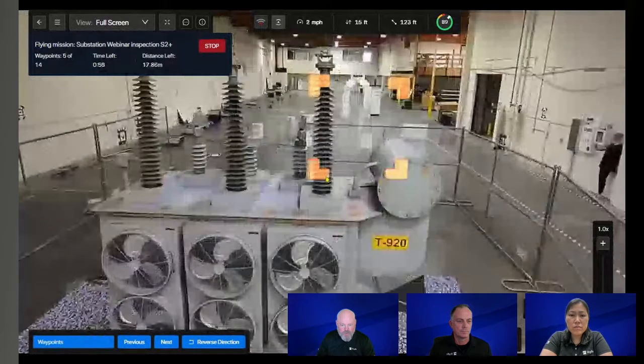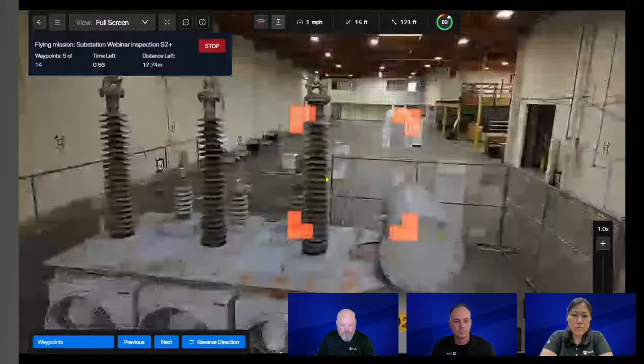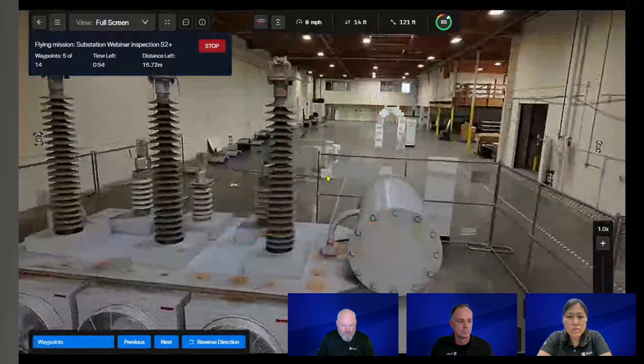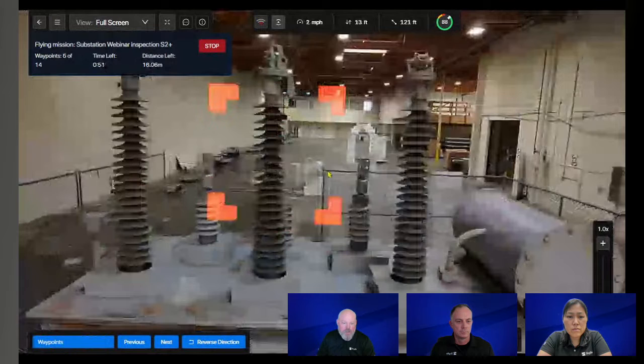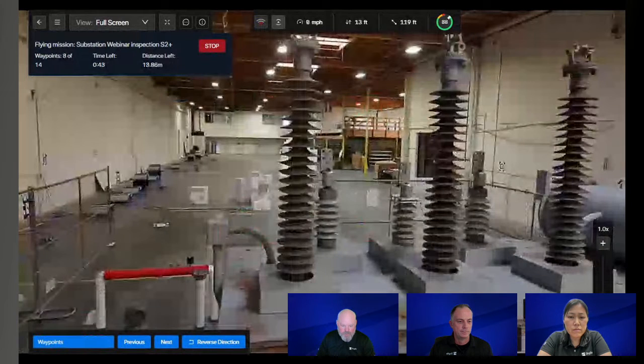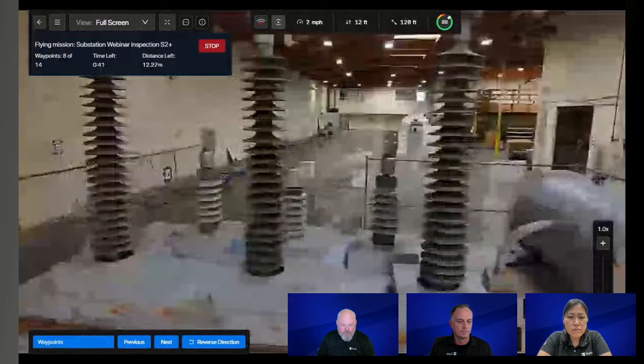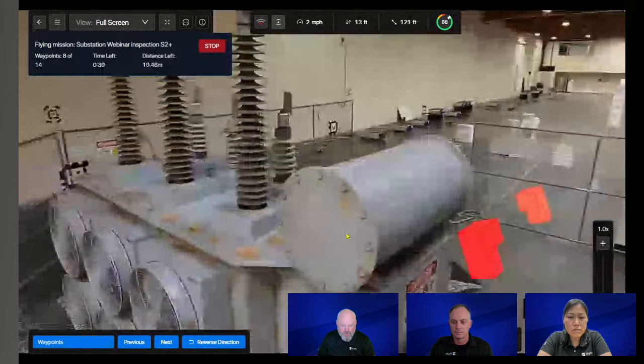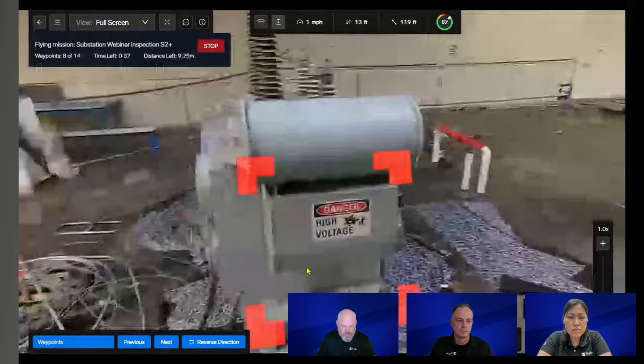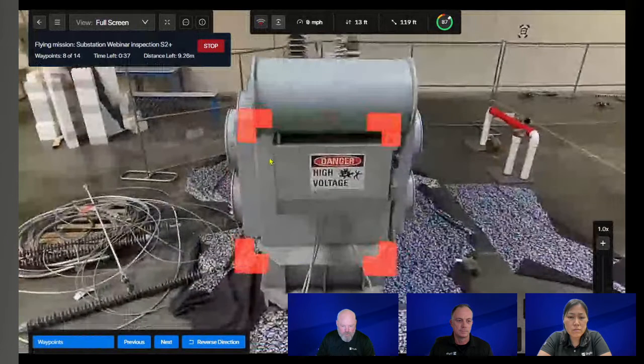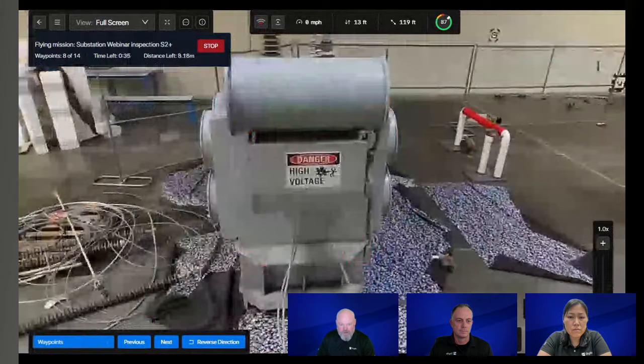So what we're doing now is zooming in on the actual high side transformer bushings. This is a repeatable inspection, something you can do and capture data in both thermal and visible spectrum, so you can have repeatable thermal data from your transformers or devices in different load states.